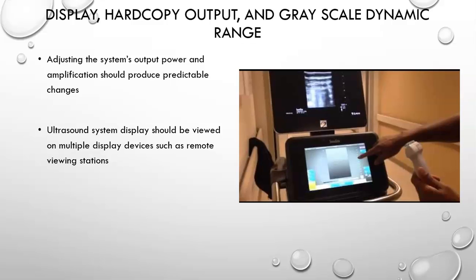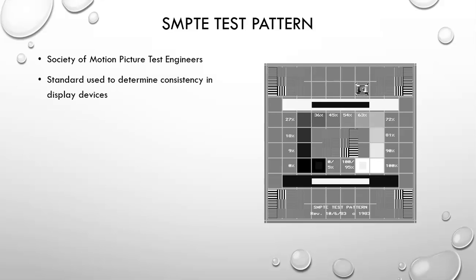So we want to make sure that our displays are good. And so we always want to make sure that once we complete our picture, that we adjust the display to match up on multiple devices such as the remote viewing stations, so it looks the same in our scan room as it does in the remote areas. And we do that with something called a SMPTE test pattern.